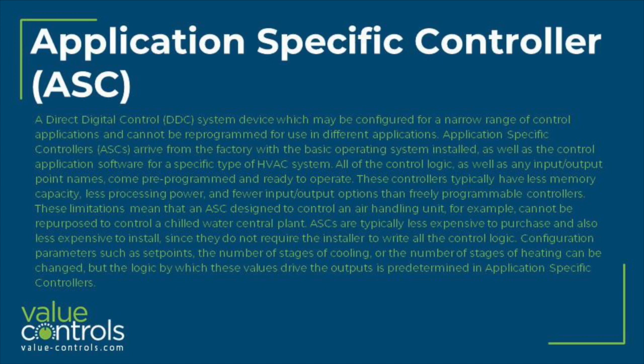These limitations mean that an ASC designed to control an air handling unit, for example, cannot be repurposed to control a chilled water central plant. ASCs are typically less expensive to purchase and also less expensive to install, since they do not require the installer to write all the control logic.